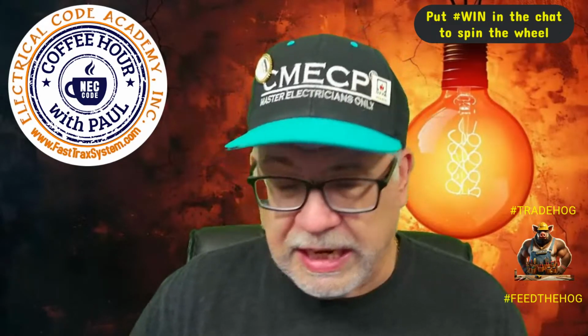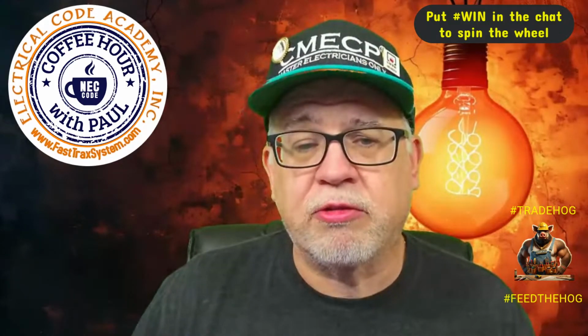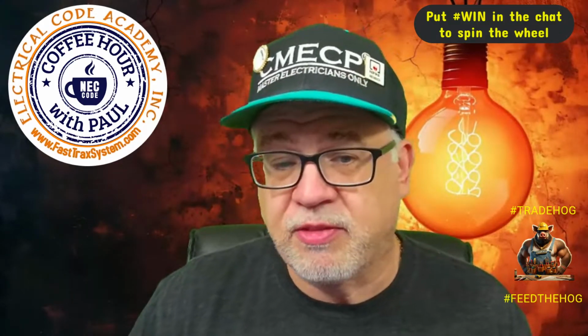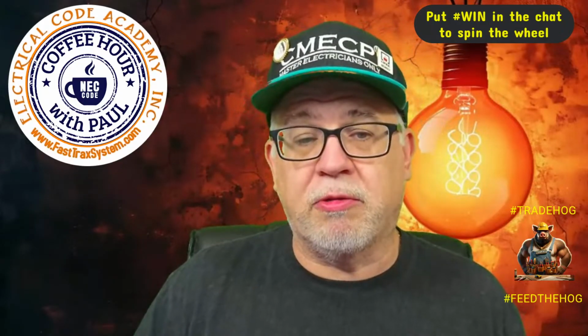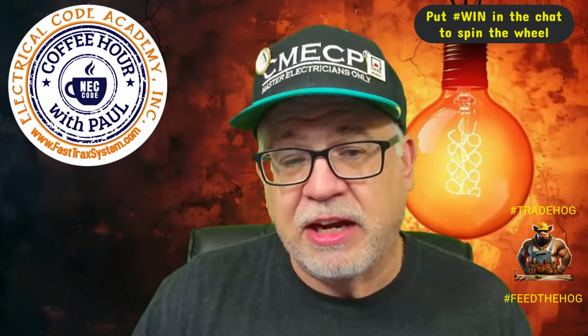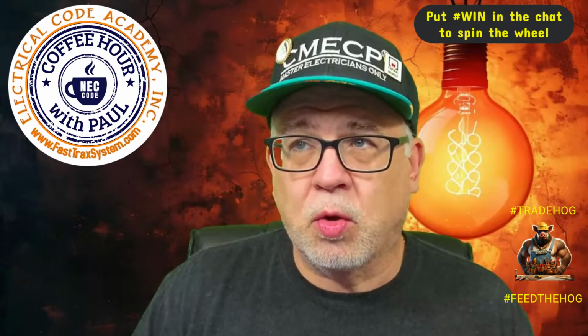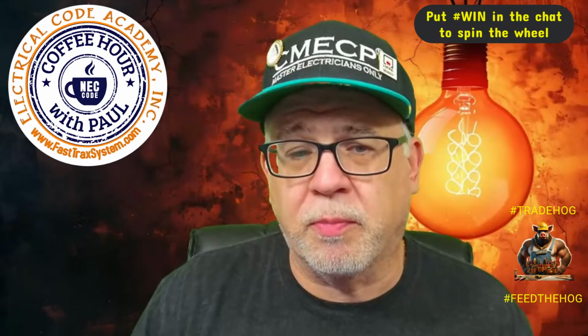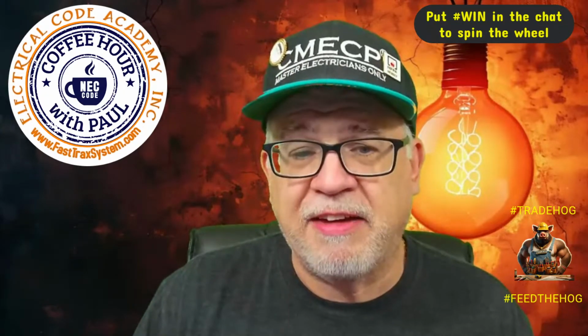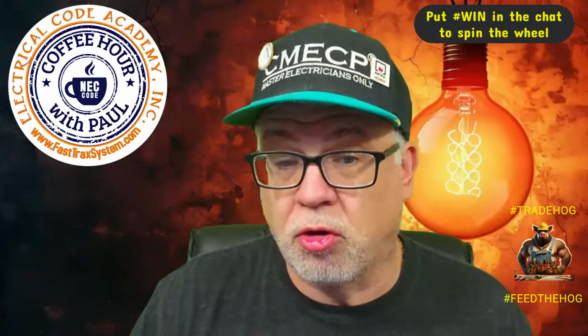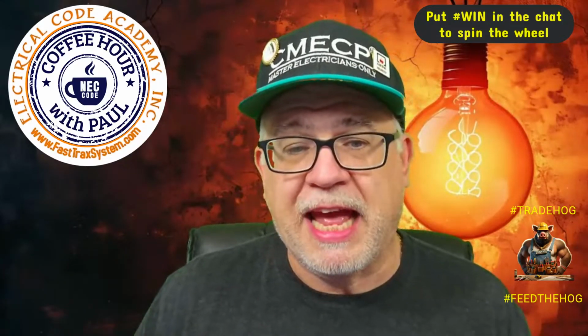Now in the 2026 code, they're introducing a Class C SP GFCI, which is supposedly going to be okay. But the question that's going to arise is, if that's a higher milliamp value, is that going to be a situation where it's no longer personnel protection because it's higher than the 5 milliamp nominal? The code panel accepted it as an option, so a lot of arguments are going to be made about that.